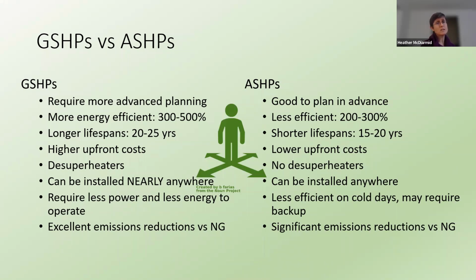From the utilities perspective, ground source heat pumps offer another big advantage: on cold winter days, air source heat pumps are less efficient because it's harder to get heat out of really cold outside air, whereas ground source heat pumps are more efficient and use less power. That means as we increase adoption of heat pumps, the more we have ground source heat pumps instead of air source heat pumps, the less electricity infrastructure we'll have to build out to meet the extra demand.